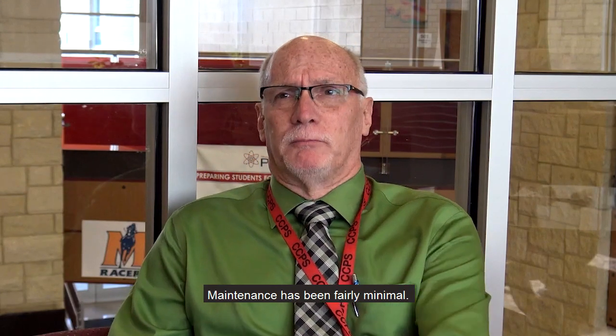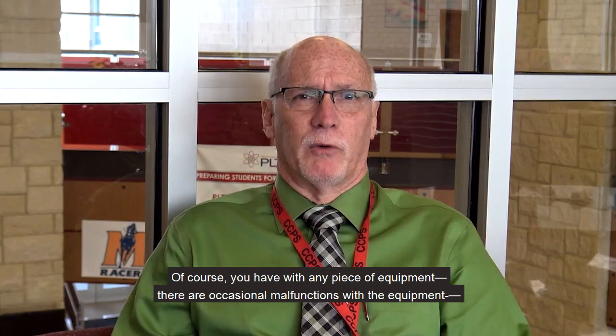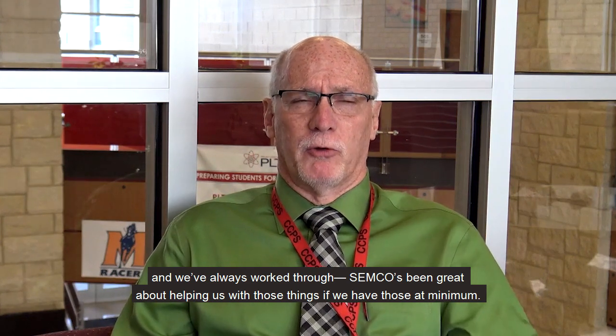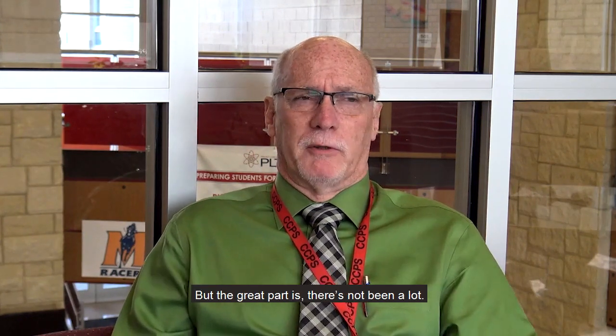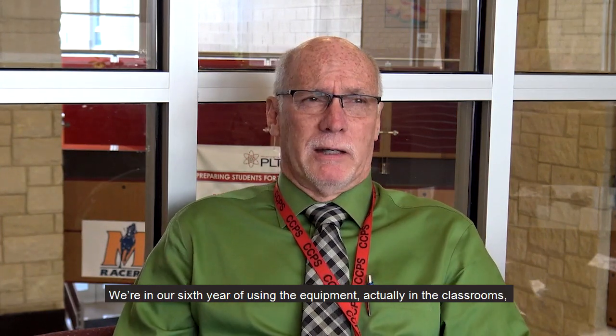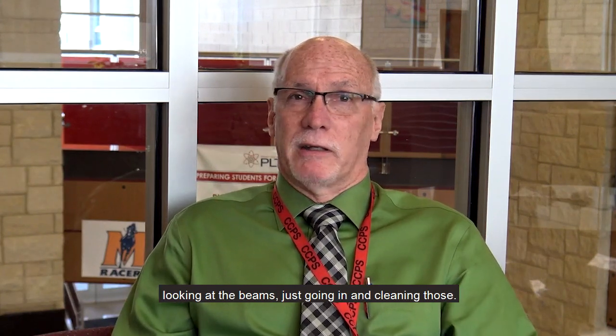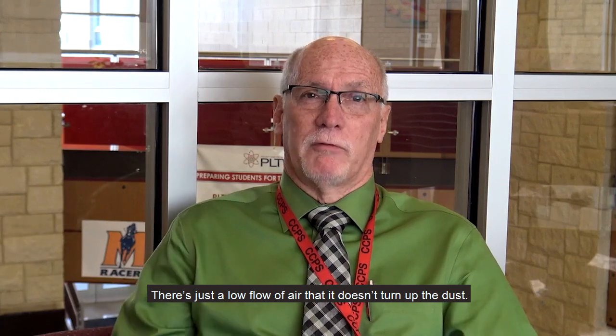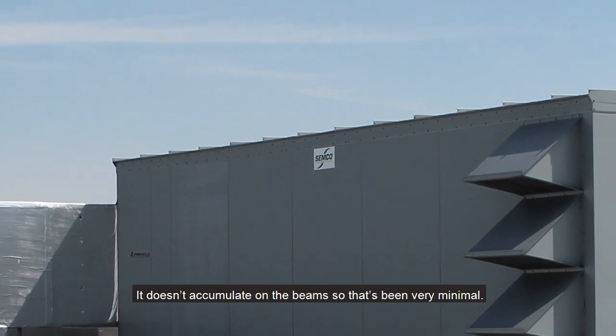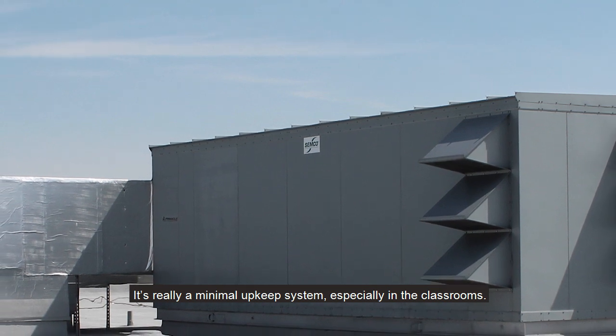Maintenance has been fairly minimal. Of course, with any piece of equipment there are occasional malfunctions, but we've always worked through them with Semco, who has been great about helping us through those things. We've had those at minimum. But the great part is there's not been a lot. We're in our sixth year of using the equipment. In the classrooms, looking at the beams, it's just going in and cleaning those. There's such a low flow of air that it doesn't turn up the dust in the room, so it doesn't accumulate on the beams. It's really a minimal upkeep system, especially in the classrooms.